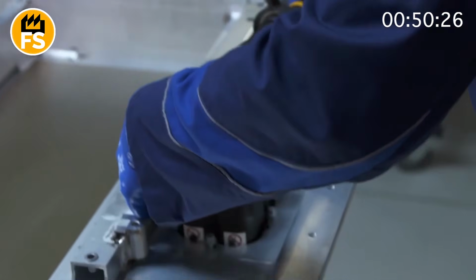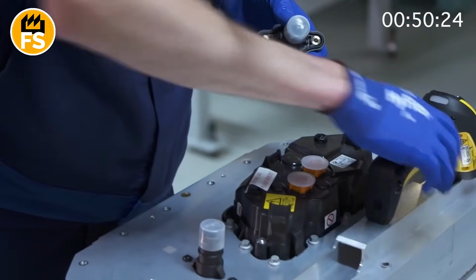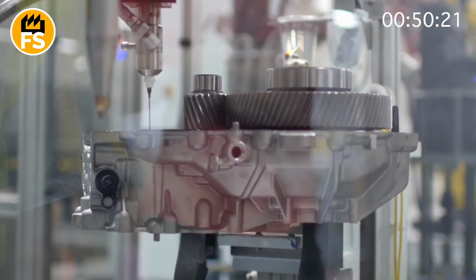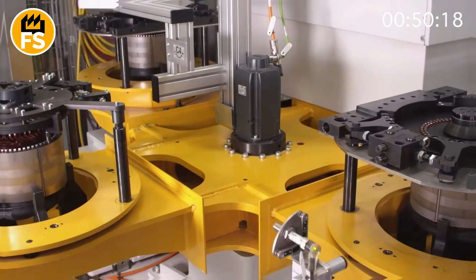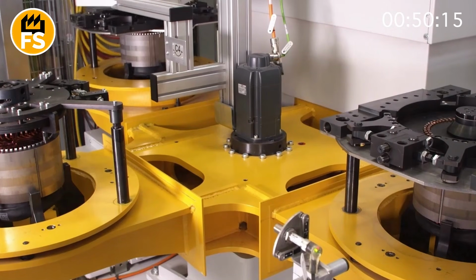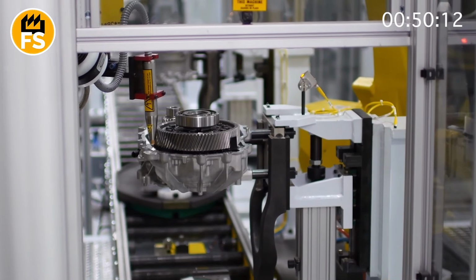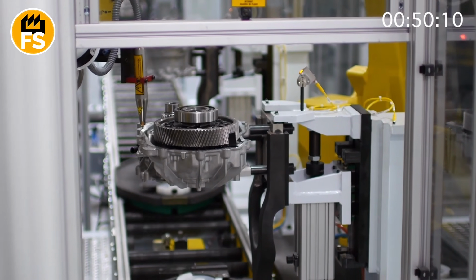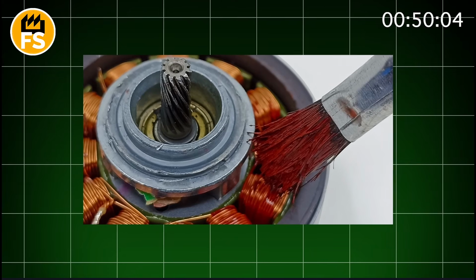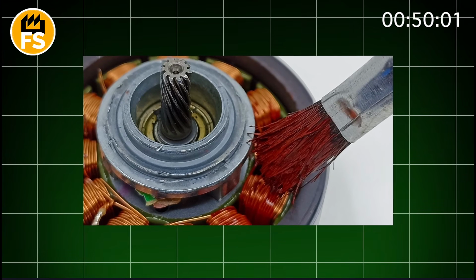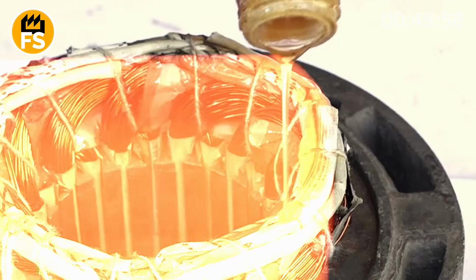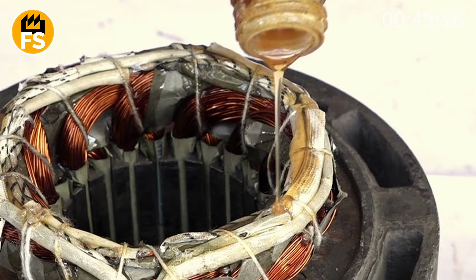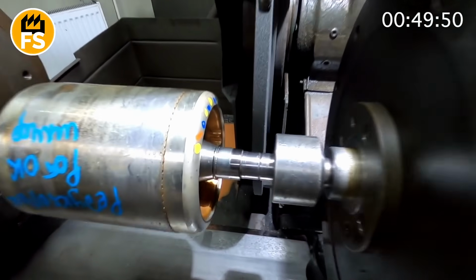In a spacious room with a specific smell of epoxy resin, the stator windings, and sometimes the rotor, are coated with electrical insulating varnish. This isn't just for dust protection. The varnish strengthens the structure, secures the wires so they don't vibrate at high speeds, and prevents moisture penetration. Application is either by dipping in a bath or by spraying. The motor is completely submerged in a tank of varnish, then removed and left to drain off the excess. Next is drying in a thermal chamber at a temperature of 250 to 300 degrees Fahrenheit. This stage resembles baking. The varnish polymerizes and forms a hard protective film.